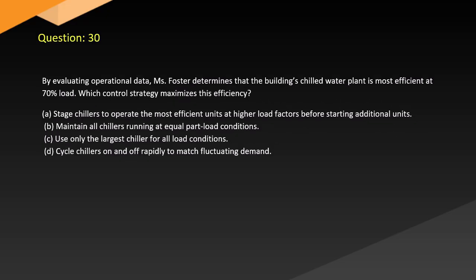Question 30. By evaluating operational data, Foster determines that the building's chilled water plant is most efficient at 70% load. Which control strategy maximizes this efficiency? A. Stage chillers to operate the most efficient units at higher load factors before starting additional units. B. Maintain all chillers running at equal part load conditions. C. Use only the largest chiller for all load conditions. D. Cycle chillers on and off rapidly to match fluctuating demand.